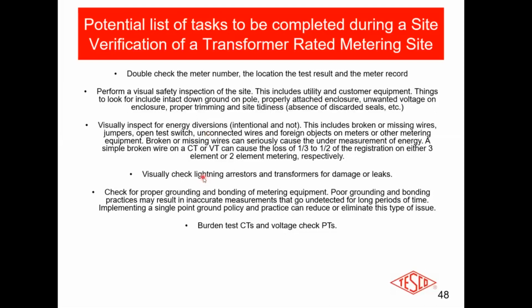Unconnected wires, foreign objects. Again, a simple broken wire can lead to a massive metering error. We're worried about 0.5% or 1% on our meter or our transformers, and yet a broken wire loses 33%. Lightning arresters, transformer checking for proper grounding, bonding, burden testing, voltage checking. You're checking everything at that site. From the way the box is mounted, once you open it up, to everything in the box, you are checking.